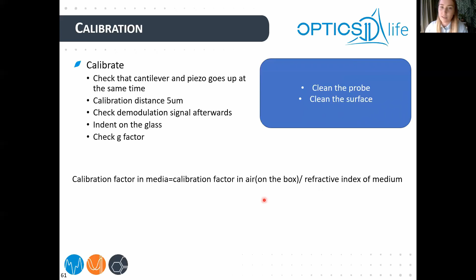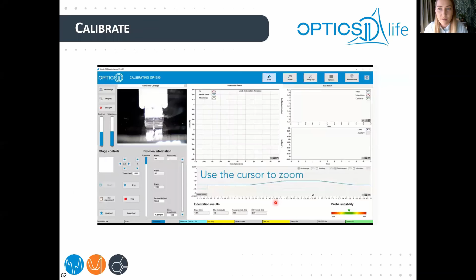And finally, the most important, check the G factor. That's called the calibration factor in the software. The calibration factor in the medium should be equal to the calibration factor in air, which is given on the box, divided by the refractive index of the medium. Yes, so that's very easy. And you should be within plus or minus 0.1. If you are off, then just clean everything and repeat the procedure.